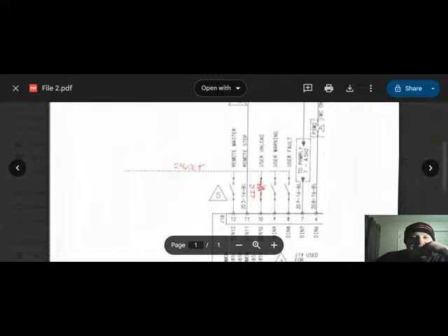So the way we would do this is we would take this 24 volt DC signal right here that's being generated by the IO module. We would run this through our relay that's been wired up and given to us by the plant electrician. So this relay is going to change states based on whether the lights are on or off. And we want to come through the normally closed of this relay to give this signal right here to input 10. Reason being, if the lights are on, this relay coil is going to be excited and it is going to change states and these contacts will open.